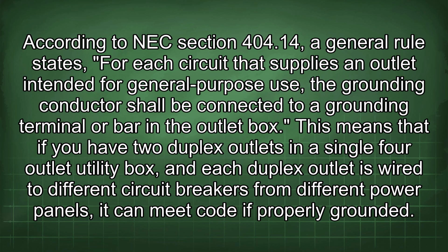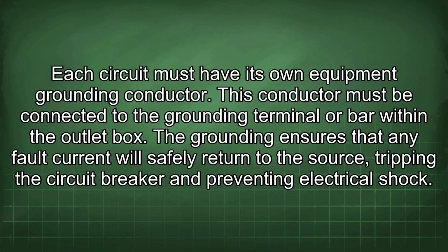This means that if you have two duplex outlets in a single 4-outlet utility box, and each duplex outlet is wired to different circuit breakers from different power panels, it can meet code if properly grounded. Each circuit must have its own equipment grounding conductor. This conductor must be connected to the grounding terminal or bar within the outlet box.